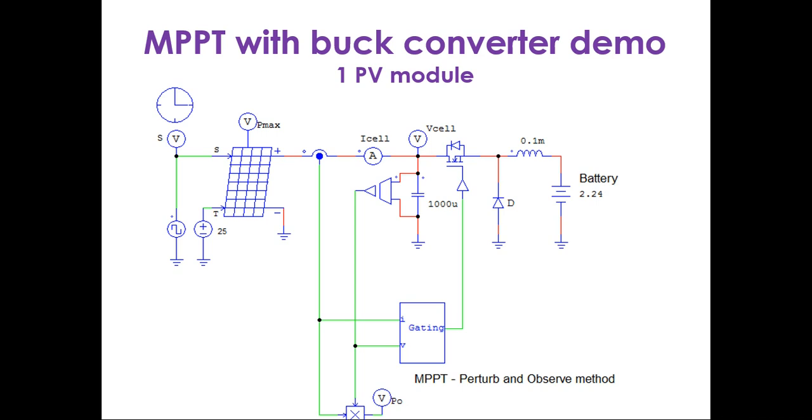Before proceeding further, the perturb and observe algorithm is used for gradually varying climatic conditions, and the incremental conductance algorithm is used for fast changing climatic conditions. It means that at locations where the radiation, temperature or the load changes in a very fast manner, particularly radiation and temperature, people will prefer incremental conductance. However, people will prefer perturb and observe where there is a gradual change in radiation.